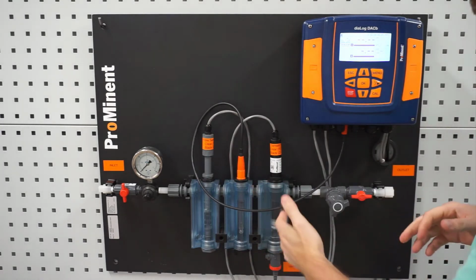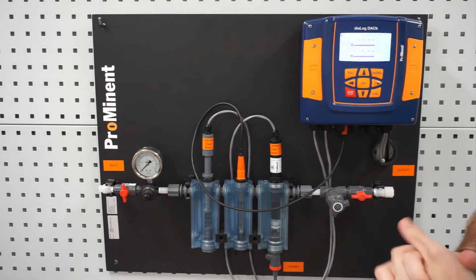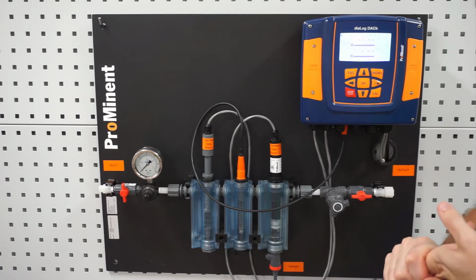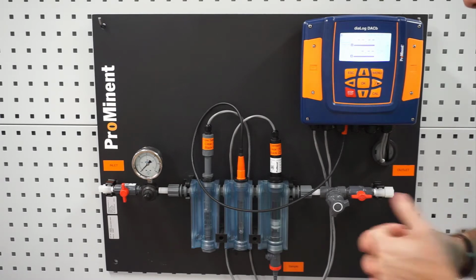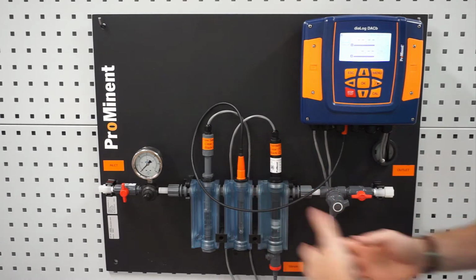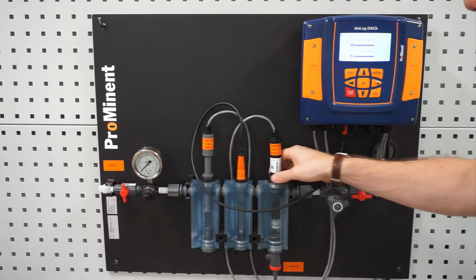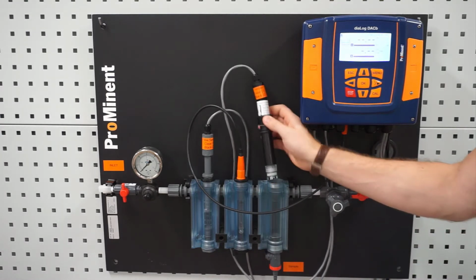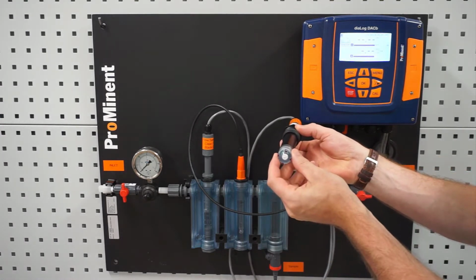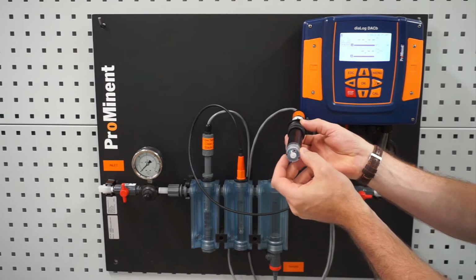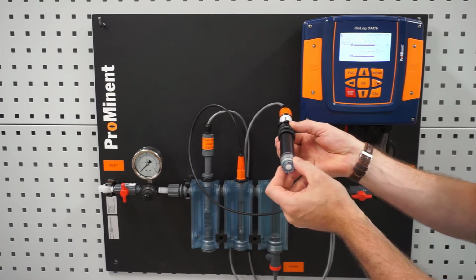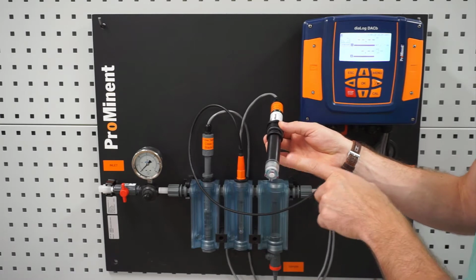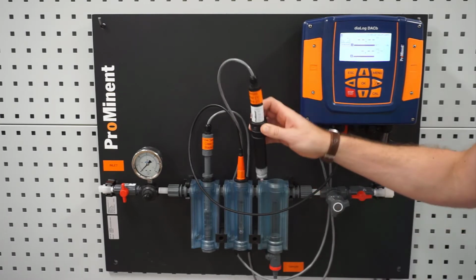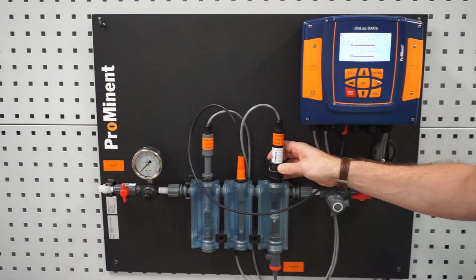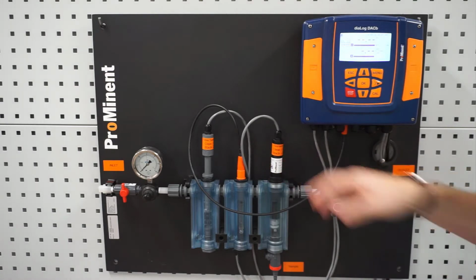And then next to that is our chlorine sensor. Your chlorine sensor is going to be pre-wired into the controller. It is also going to ship in the DGMA cell. It does require that you pull it out and gel the electrolyte. So you will get a separate box with the electrolyte in it. You will need to go through the process of gelling up that sensor. And I'll show you a short clip here on what that process looks like.